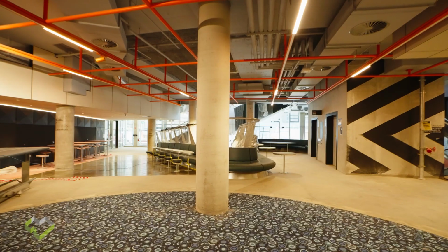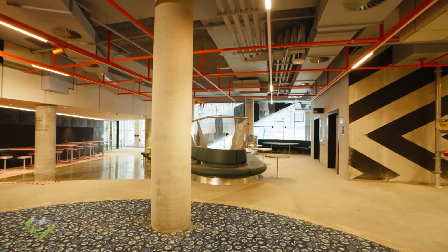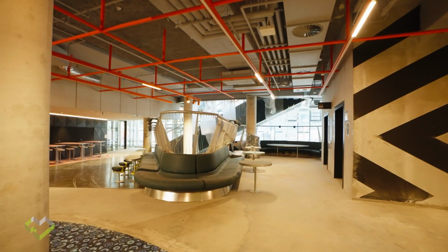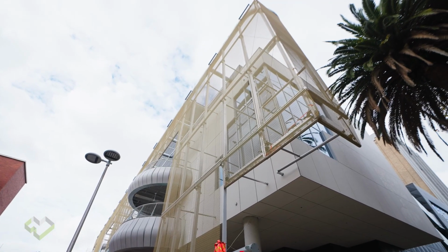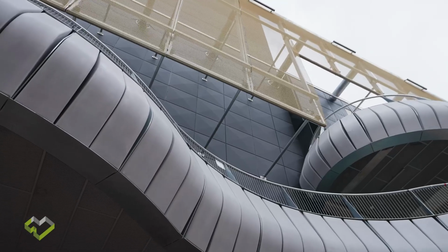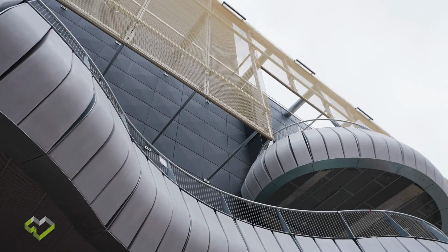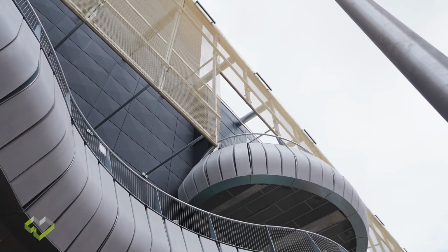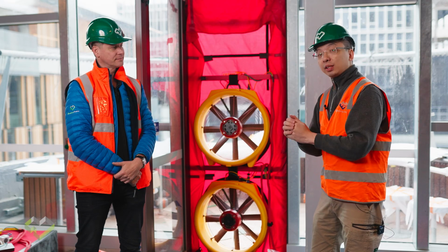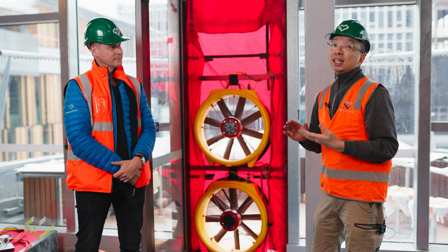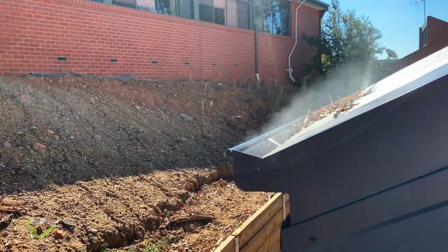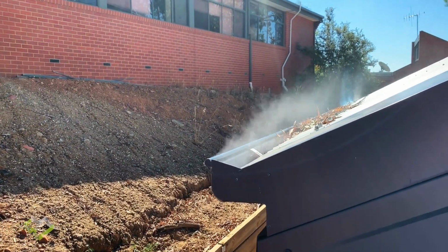For example, if you've got thousands of tiny holes, when the air around the building is still, the actual energy loss may be very small, because it doesn't have the drive to push the air through those small holes. But if you've got bigger holes, particularly at high level near the ceiling, then in winter you lose the majority of your heating through those holes. Your building just becomes a big chimney.